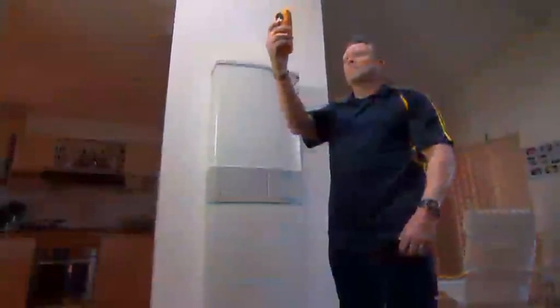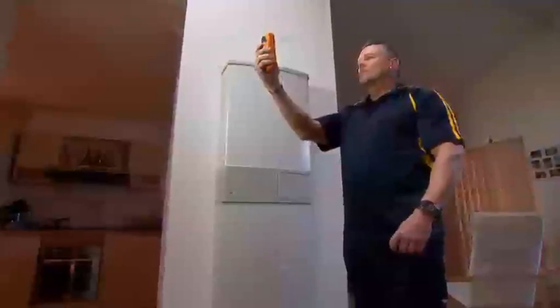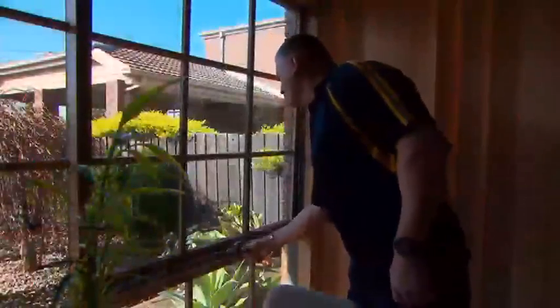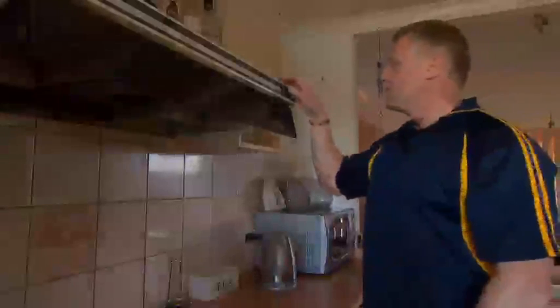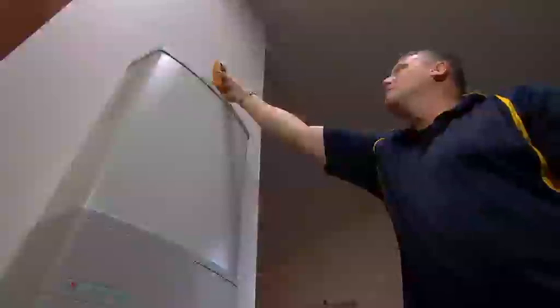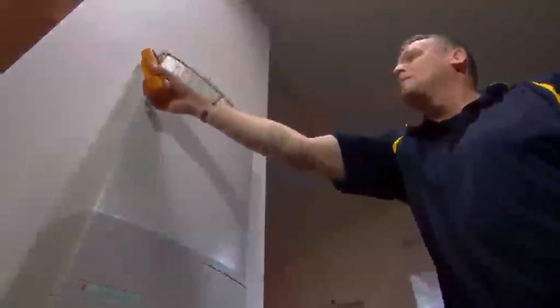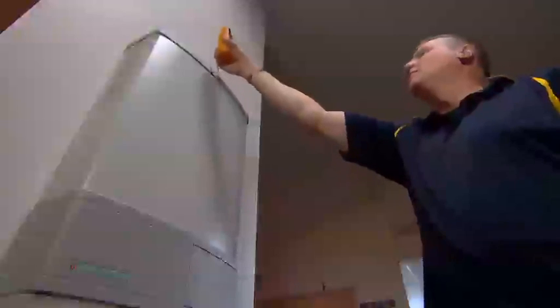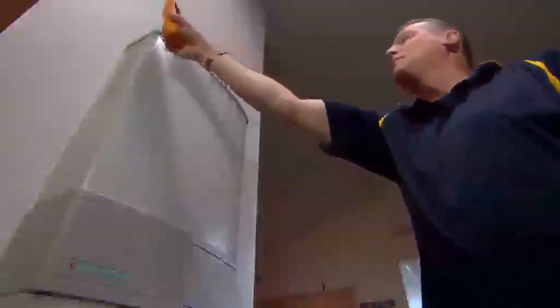Leave the appliance operating at maximum gas consumption. Shut all windows and exterior doors, and then turn on exhaust and extraction fans, one at a time. After turning on each fan, check for CO by passing the detection equipment sampling probe over the draft diverter relief openings. If the appliance room fan can be turned down, then set the appliance room fan to the lower setting and check for CO again at the draft diverter relief openings.